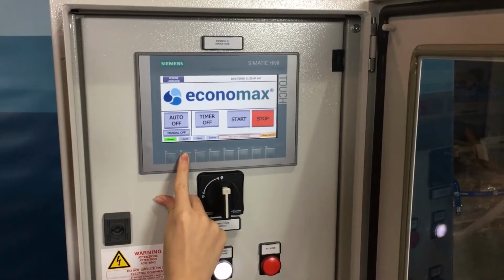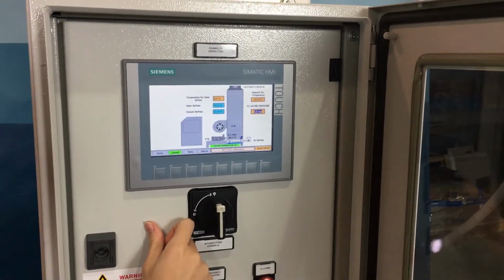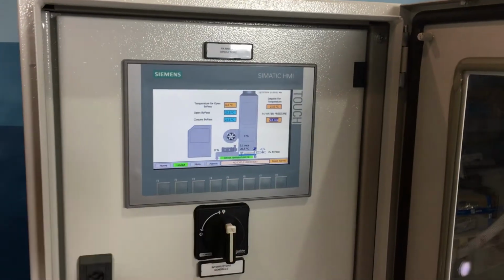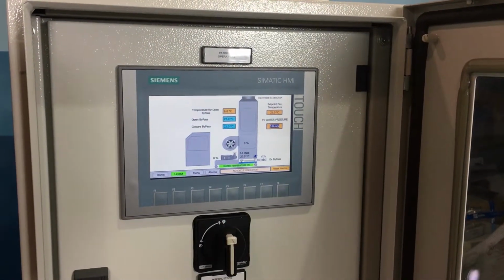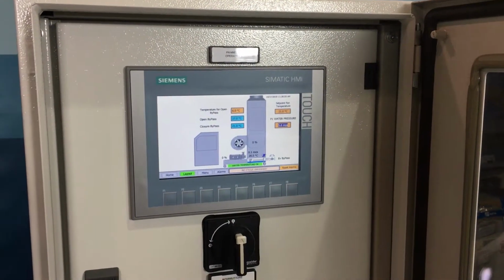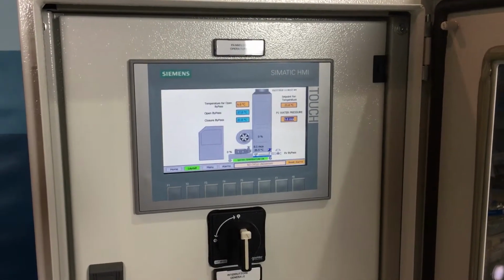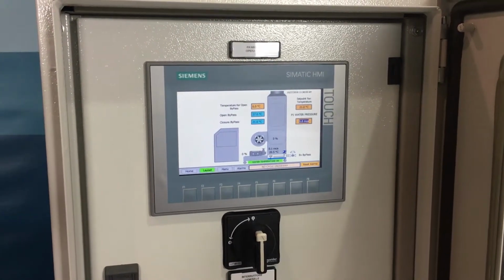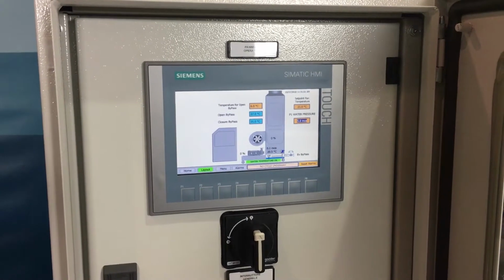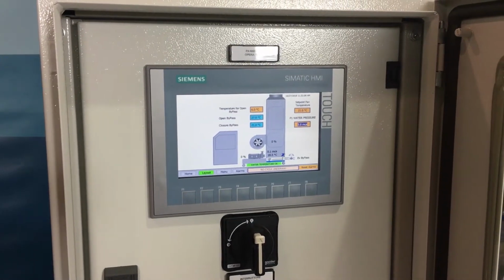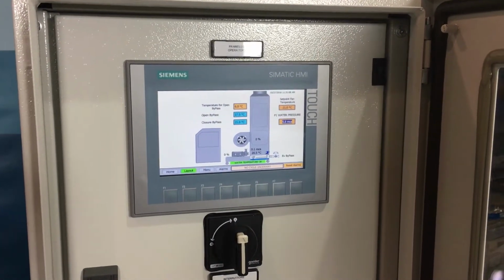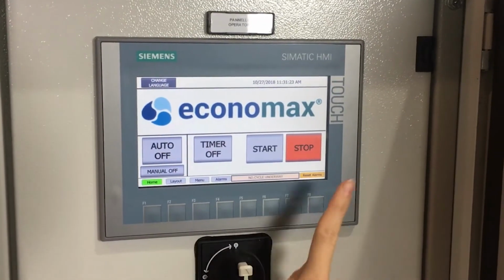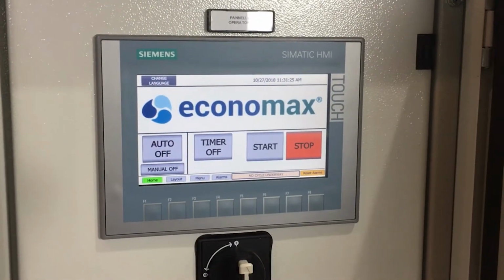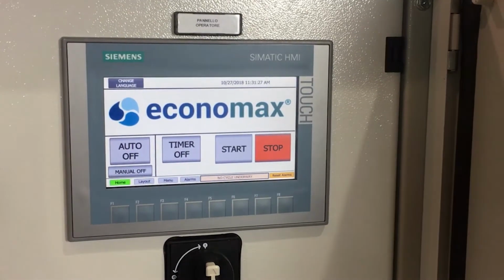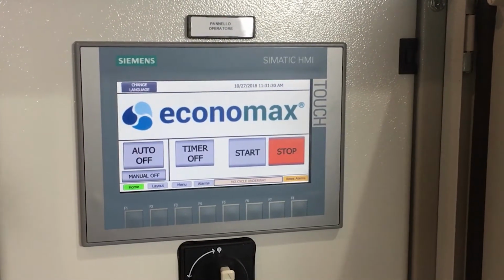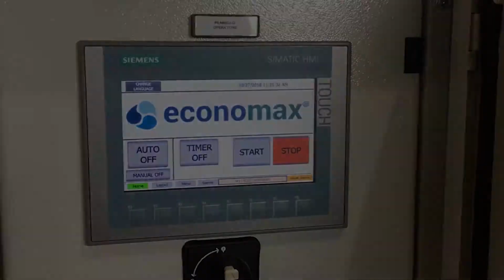By pushing the F2 button, you can access the layout screen that allows you to monitor the parameters of the entire machine and system. Through this screen, you can always control the tower's functioning parameters and check the pump and fan speed, as well as water pressure and temperature. With the F4 and F8 buttons, you can access the Alarms menu, where all the alarms are shown in case of needed maintenance or malfunctioning.